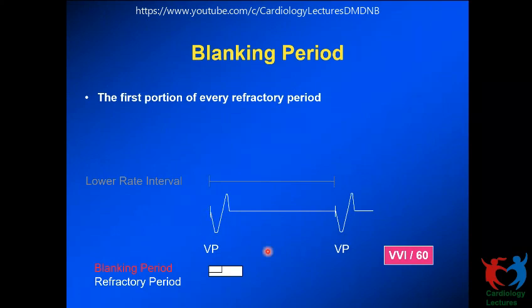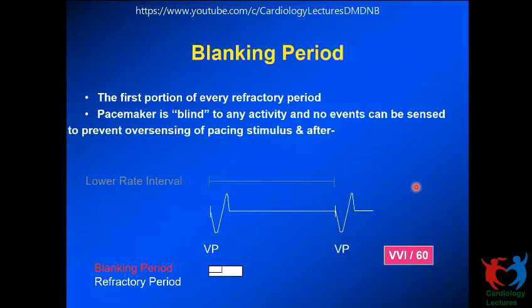And the same thing will happen after a sensed event also. The question is, why do we want that blanking in a sensed event? There is an R wave that's happening, changing frequently at a high frequency. We don't want to sense all over again. There is no fear of the sensing circuitry getting damaged, but we don't want to continuously sense that noise that's happening. And that's why it's blanked after a sensing event as well. So on a paced event or a sensed event, it starts a refractory period, which is a programmable one. The first portion of that is the blanking period, during which the pacemaker does not sense anything. But during the refractory period, the pacemaker might sense, typically a T wave or a PVC, that will be ignored by the pacemaker, and then it would start one more refractory period. That's the blanking and the refractory period.